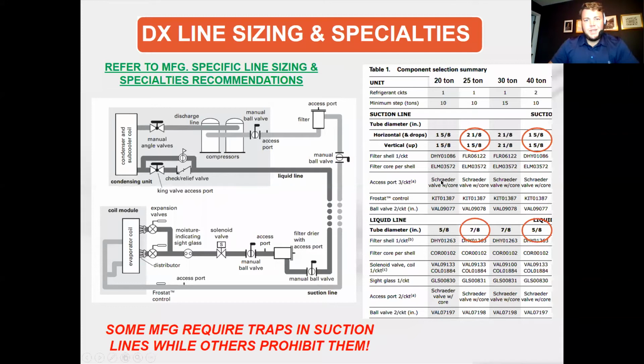Obviously, the more detail, the better. Mike's going to talk a little bit about some of the pros and cons of getting into more detail as a designer versus the installer. So we'll touch on that. But here's a great example of a very diagrammatic split system, including specialties and equipment components. And so, as I mentioned before, 4 basic components here: compressors, and TXV. But there's all sorts of things that go in between. You have suction filters in order to make sure the refrigerant stays clean, shutoff valves, liquid filters, solenoid valves to avoid refrigerant migration during the off cycles. Moisture sight glasses, expansion valves are very important to select and size properly, 1 per distributor on the evaporator coil.